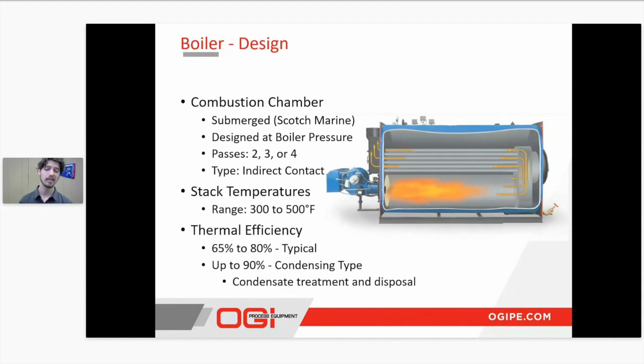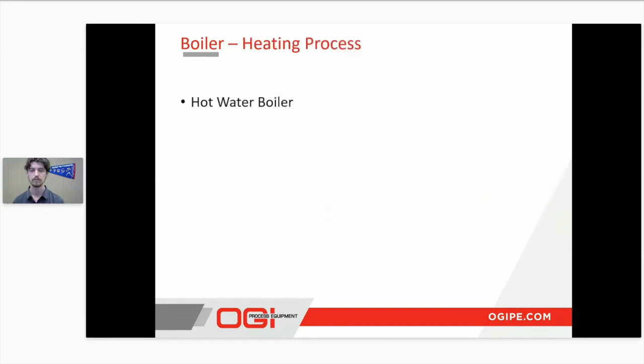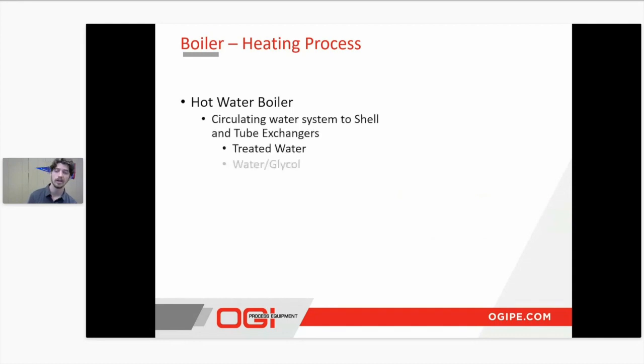And then you can increase the performance of your boiler by using a condensate treatment, such as an economizer, to gather back some of that condensing water. As far as the heating process goes, in a hot water boiler, you're going to have that circulating system going around the shell and tube exchangers, typically with a treated water or a water glycol.